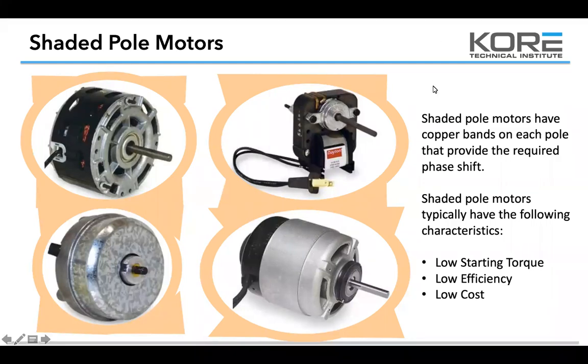Shaded pole motors have copper bands on each pole. That copper band gets magnetized from the electrical current. That's where you get that shaded pole. It's on one side of the windings, or it's offset, and so it throws the rotor in a specific direction, and that's what causes your rotation.